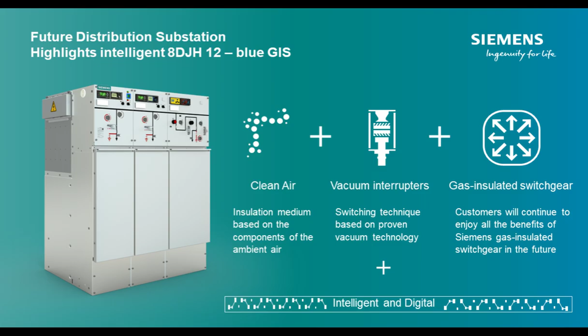So what makes this ring main unit also intelligent and digital? As we have it installed in the future distribution substation, we have remotely controllable switch disconnectors and circuit breakers. There are installed intelligent short circuit and earth fault direction indicators, as well as a digital transformer protection device. One important aspect is the measuring of current and voltage, which is realized in our solution with so-called low power non-conventional instrument transformers for current measurement, which provide a very high accuracy for the current, and we have high accuracy also with the voltage measuring via resistive voltage dividers.